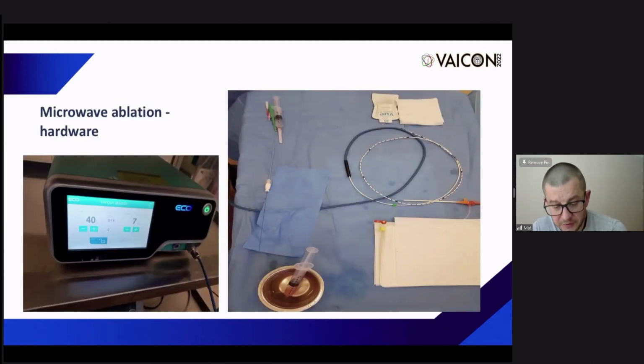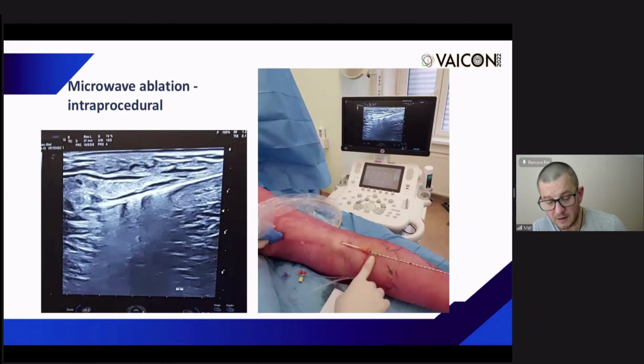In our institution, we use a microwave system produced by Ecomedical Instruments, China. It consists of a dedicated microwave generator unit and a disposable, soft tip, flexible, not sterilizable microwave probe. When introducing the probe into the vein, a 7 French introducer sheath is needed.